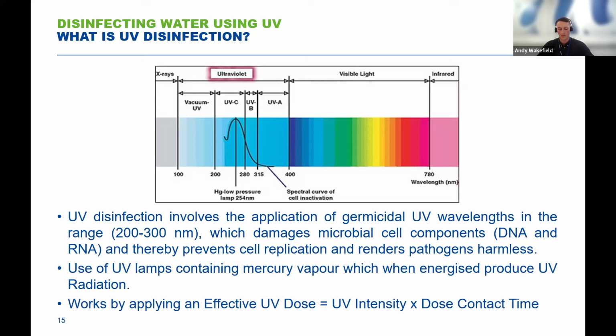One of the issues with UV is that it does not impart a residual within the water itself, so it's a contact time process. UV dose is the effective application of UV to a cell, and this is measured by the intensity of the UV and the contact time. We typically use UV reactors containing UV lamps to produce the UV radiation, and typically it's installed either with the water flowing through the reactor or with the reactor lamps placed in a channel or something along those lines.